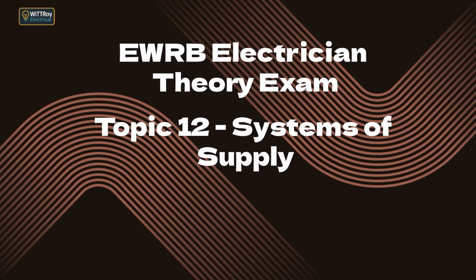12.1b. State the typical voltages involved in each of the above areas. Typical New Zealand supply voltages include 11 to 18 kilovolts at generation, 110 kilovolts and 220 kilovolts for transmission, 33 kilovolts for sub-transmission, 11 kilovolts for local distribution, 400 V three-phase and 230 V single-phase for final consumer supply. These values are important to remember for both practical work and exam questions.